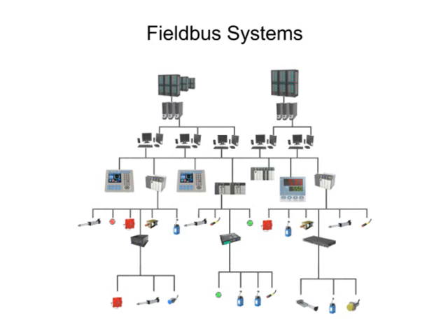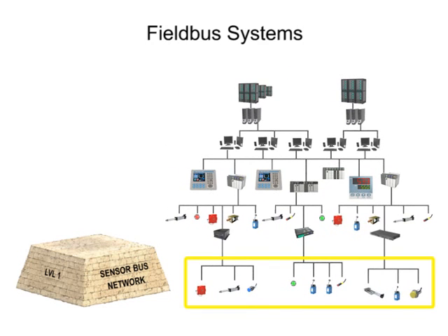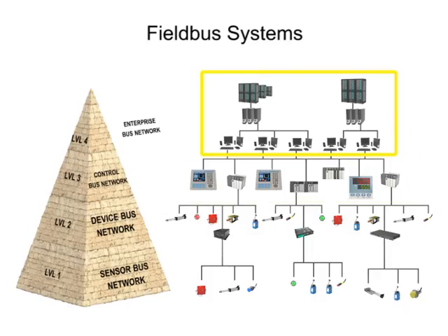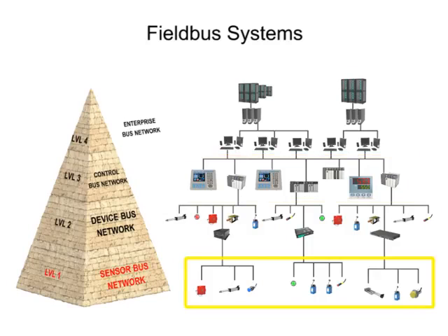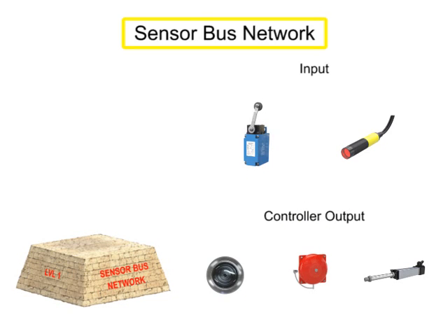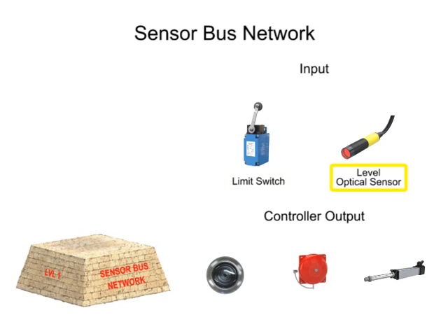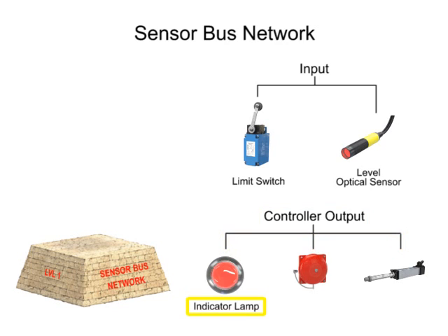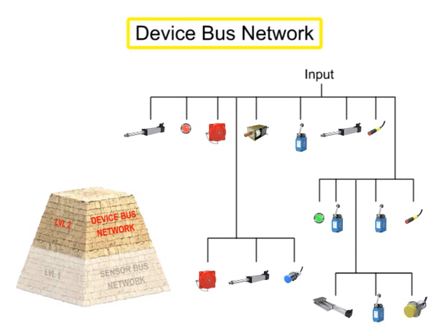Fieldbus industrial networks can be broken down into four levels, each with increasing levels of complexity. The most basic level is the sensorbus network. Sensorbus networks are the least complex networks developed for industrial application. Multiple basic field devices like limit switches or optical sensors are connected to one network cable, and the sensorbus network is also capable of transmitting output signals from the controller over one cable to indicator lamps, alarms, or other actuator devices.